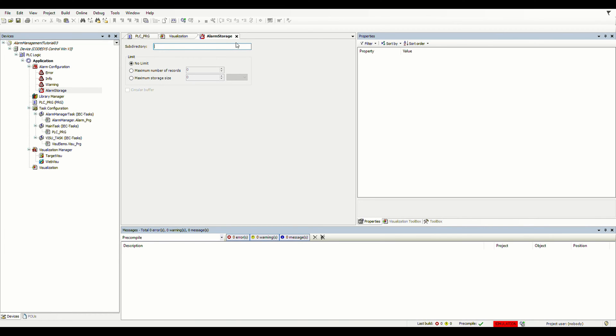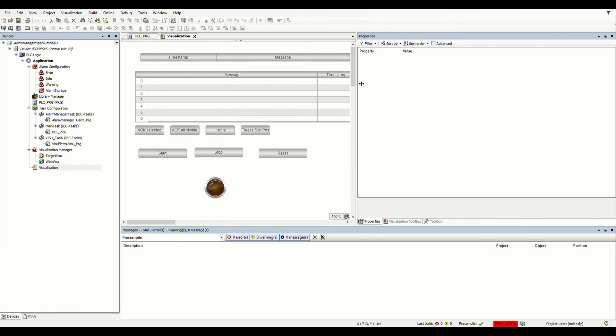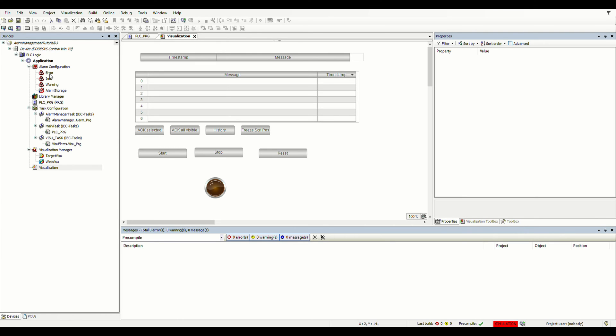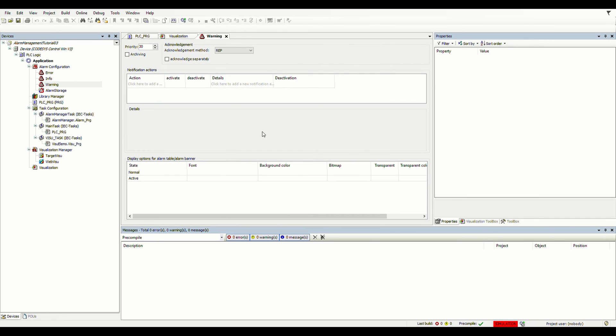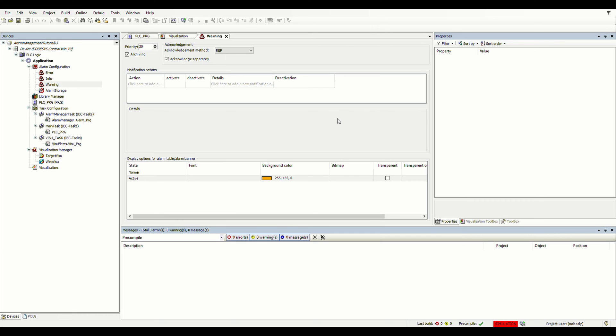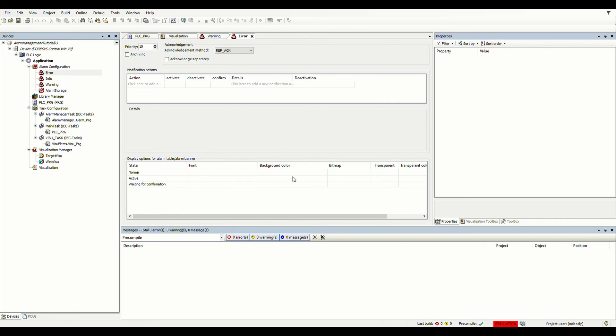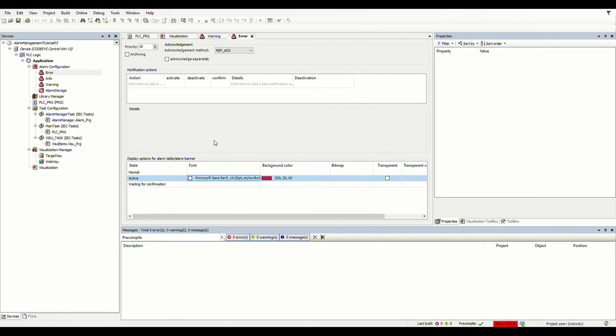I'll keep the defaults for alarm storage — I don't want to set a subdirectory for storing or any limits. For the warning class, I'm telling the system that when such an alarm happens, I want to receive the message with an orange background color and a black bold font at size 14. For the error class, I want a red background and white font. For both of them I have archiving and acknowledge separately selected. These are the classes I'm going to use.